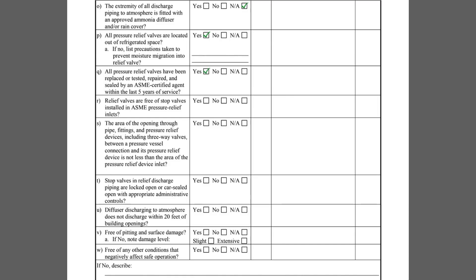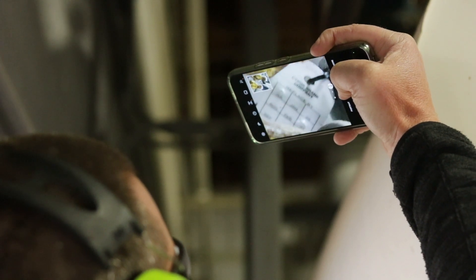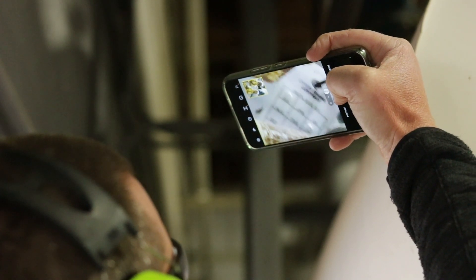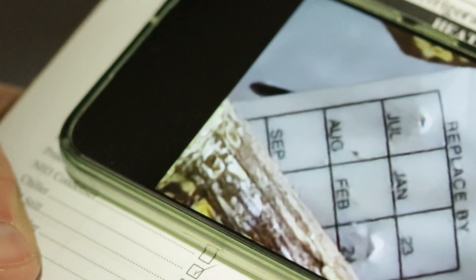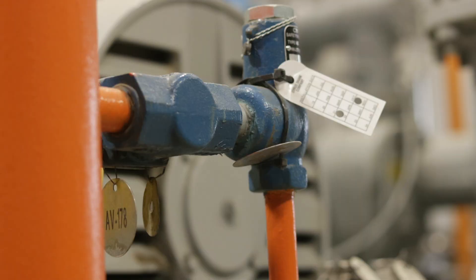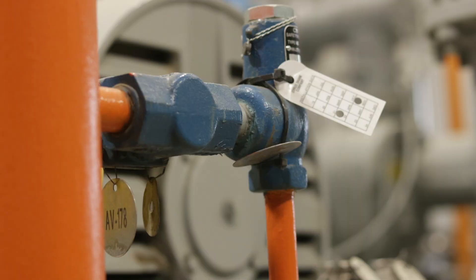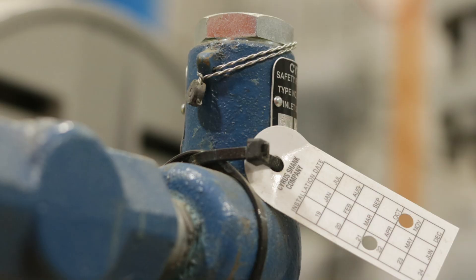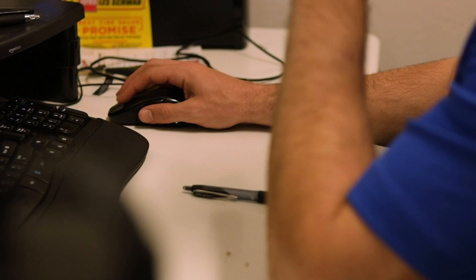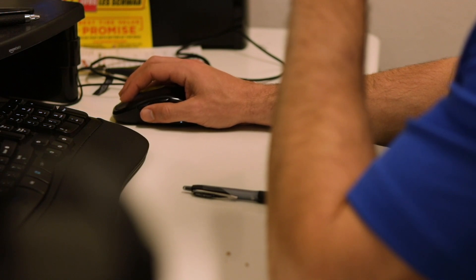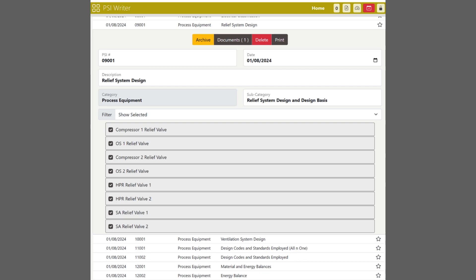Item Q asks if all pressure relief valves have been replaced or tested, repaired, and sealed by an ASME certified agent within the last five years of service. For ammonia refrigeration systems, the most common practice is to replace relief valves every five years. The easiest way to check is by examining the date tag attached to the valve, which is punched on its installed date and indicates when the next replacement is due. It is recommended to have another means of keeping record of the installation dates in the event that a date tag becomes detached.